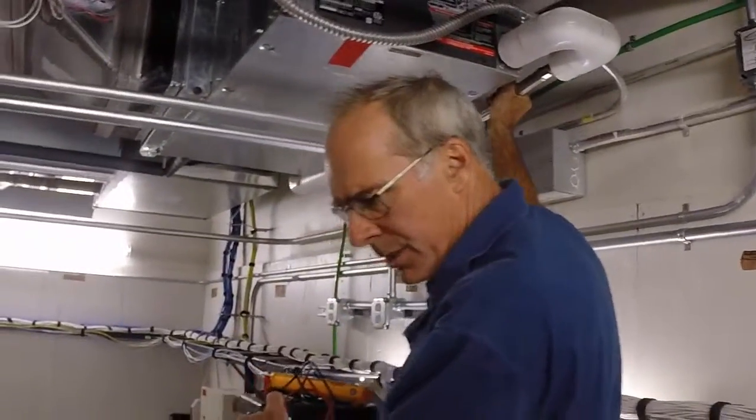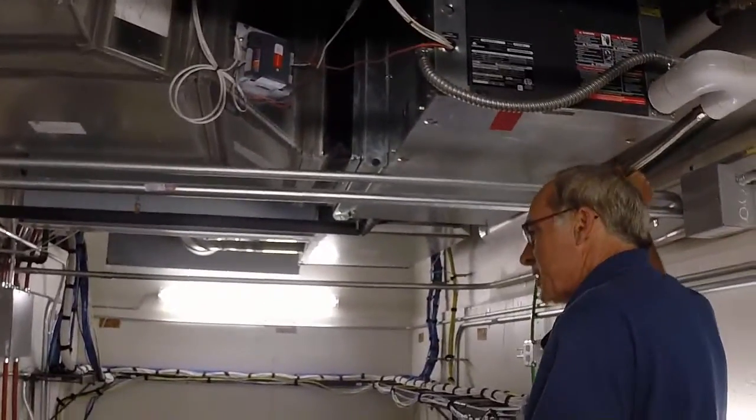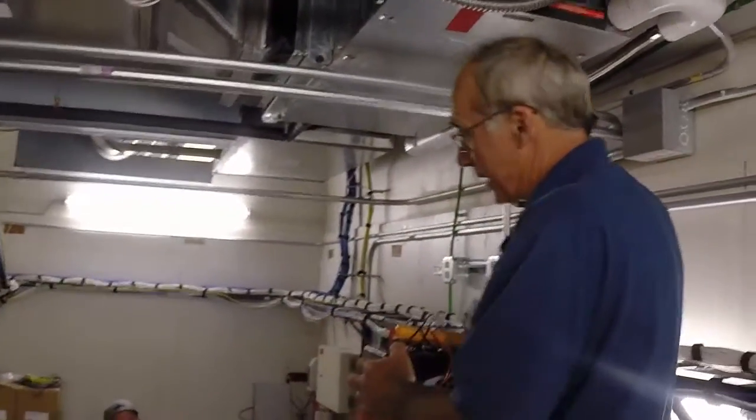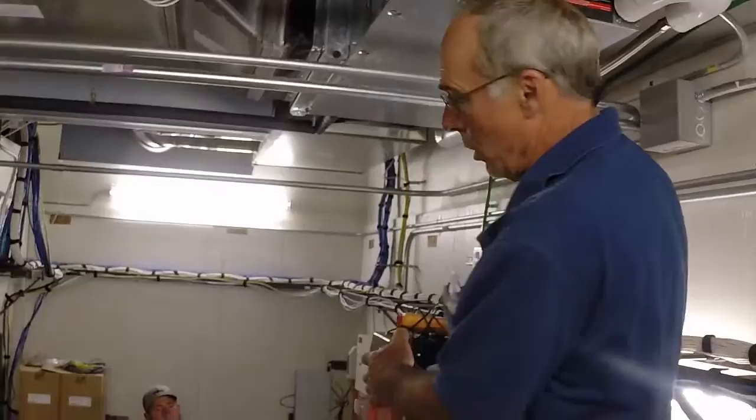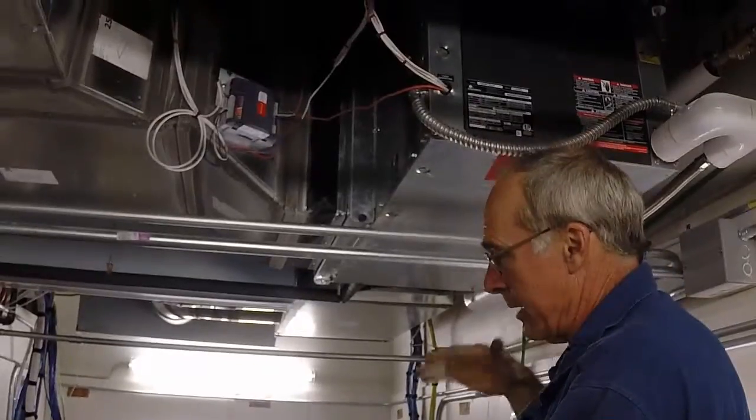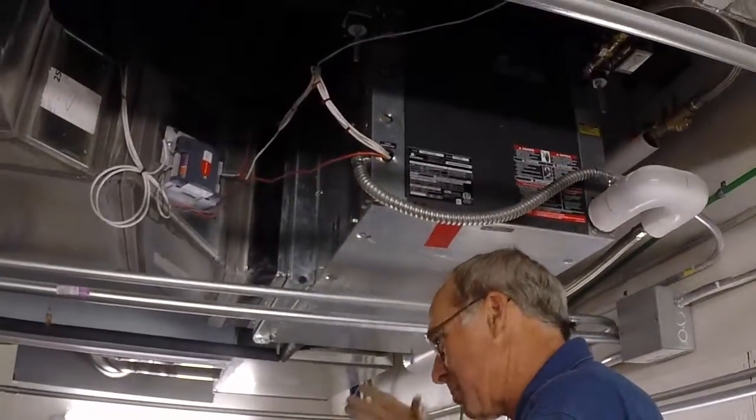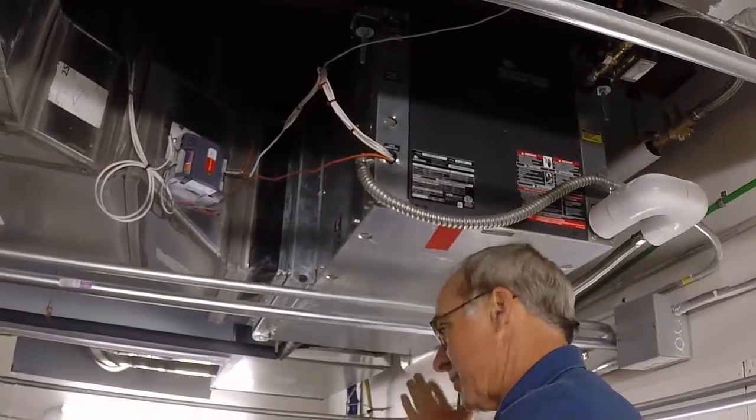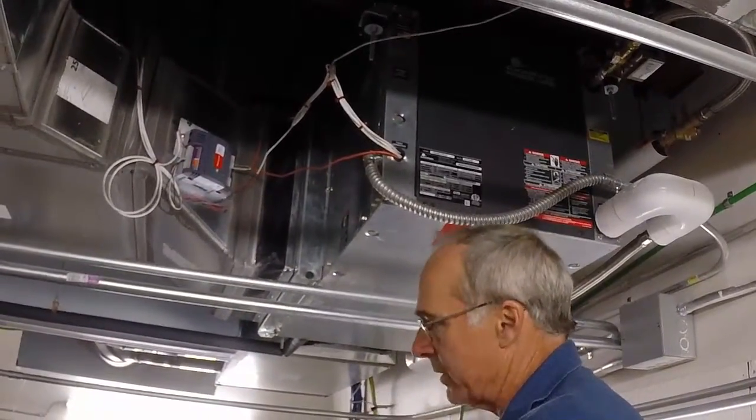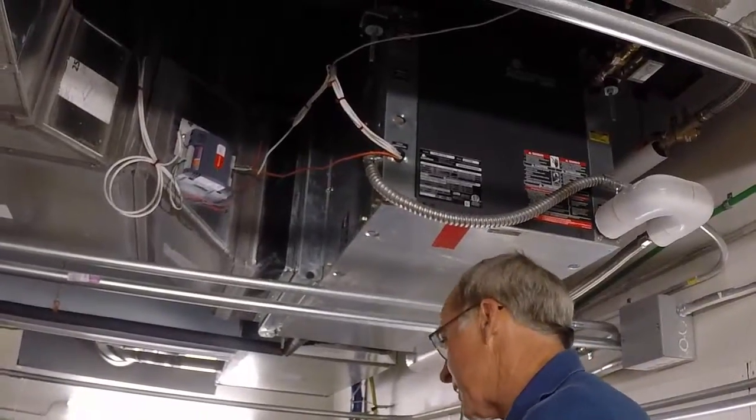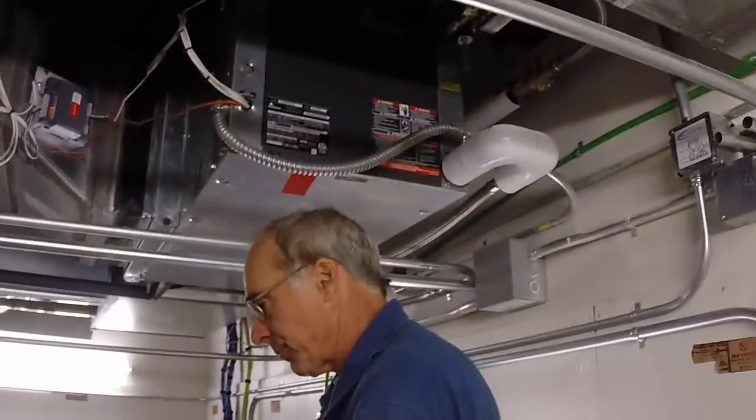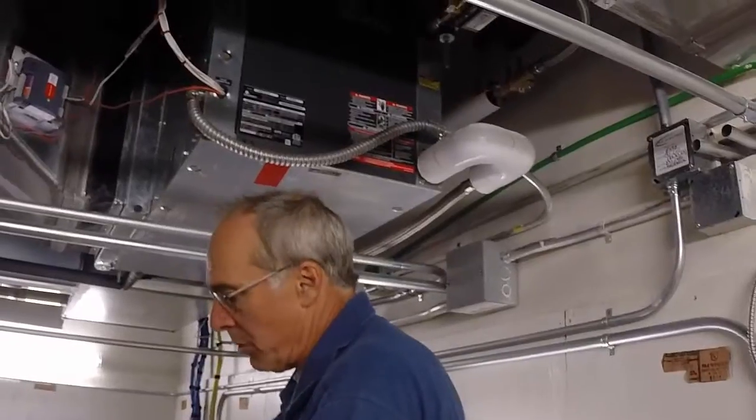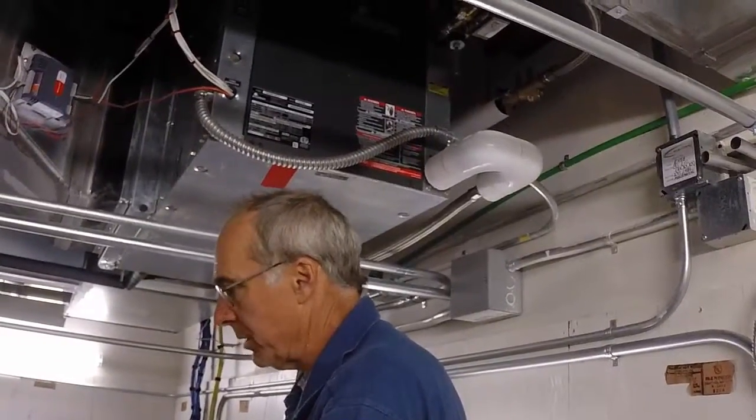In the winter months, you don't want to see this water get below about 35, 40. You have 50/50 glycol, so there's a jumper that you cut on the board. With glycol you can go colder, but anytime you get 20 degree water, I'm putting out crap, no heat coming out of it. The optimum temperature is about 65, 70 degrees. It's a great range to be in for the water loop. In the summer months it can actually go up to 75, 80 if it has to.